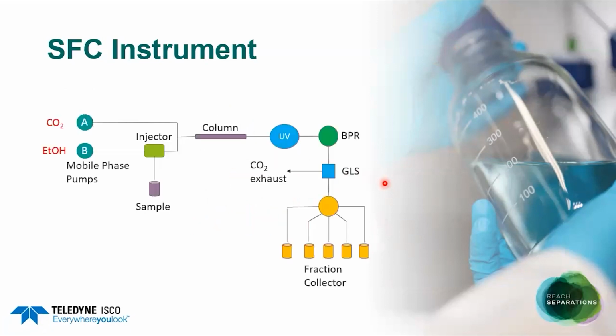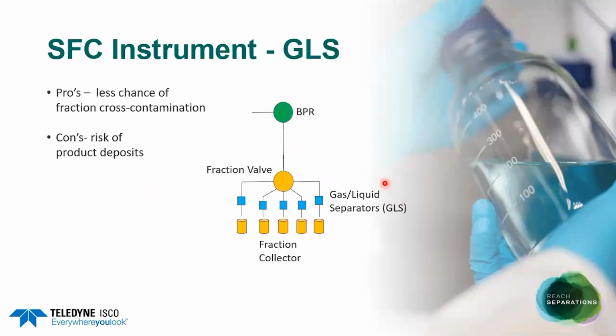So if we go back to the overall layout of the SFC system here, you can see in the picture there are other additions that you need for an SFC system, such as chiller blocks on the CO2 and heat exchangers, but the main crux of the flow path is depicted on the slide just here. If we now focus back in on the gas liquid separators, this brings us on quite nicely to some of the features of the ACCQPrep SFC system. As I mentioned earlier about the two possible configurations for a GLS, the first one being having one GLS per fraction valve.